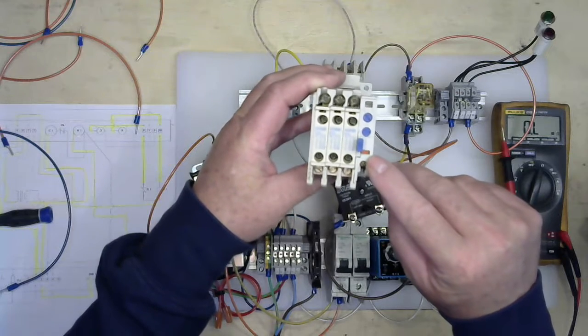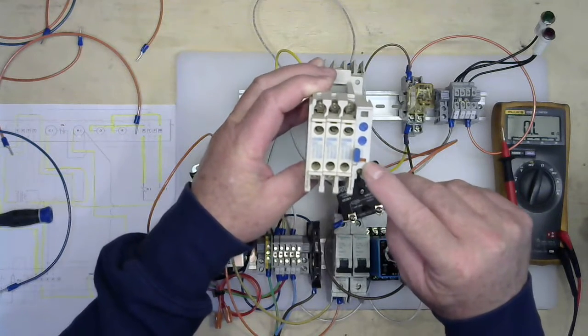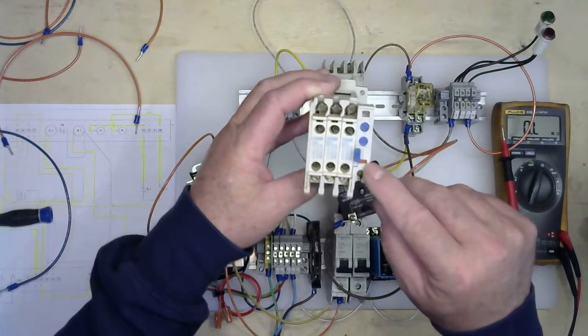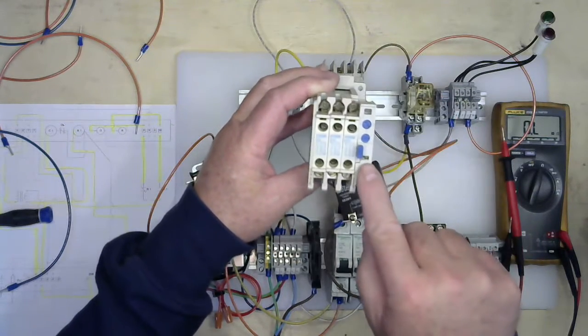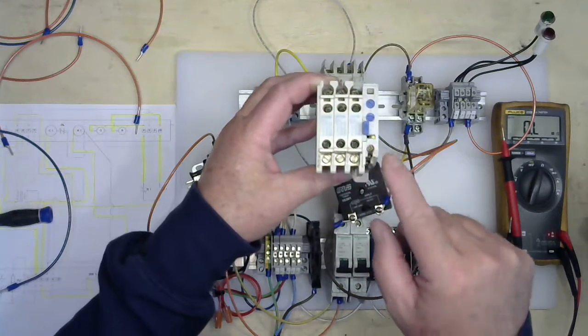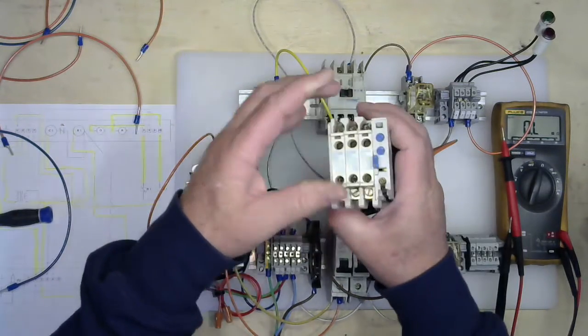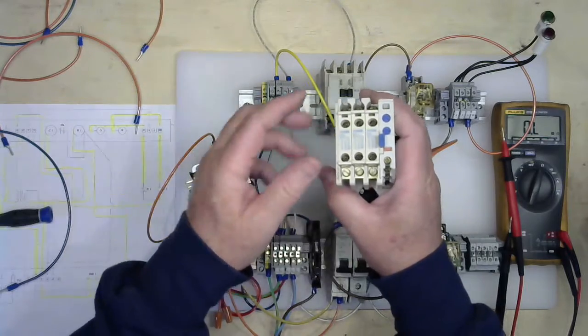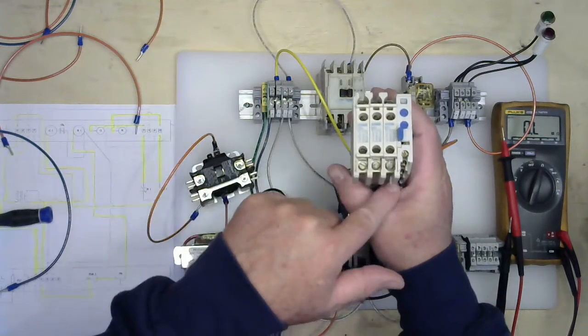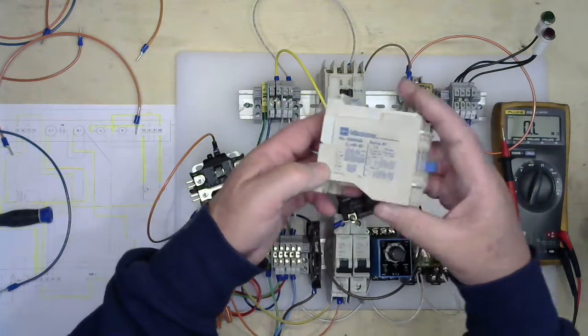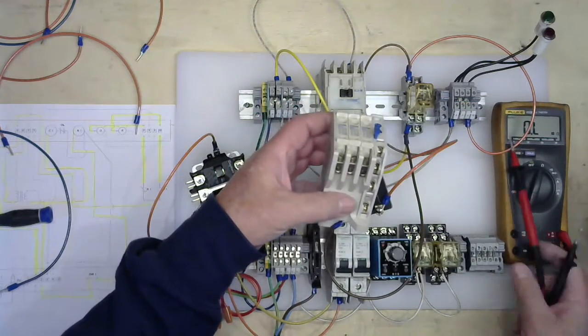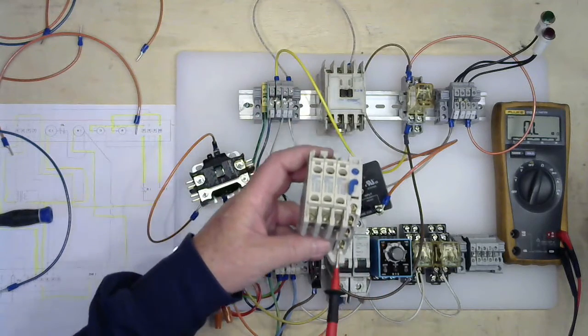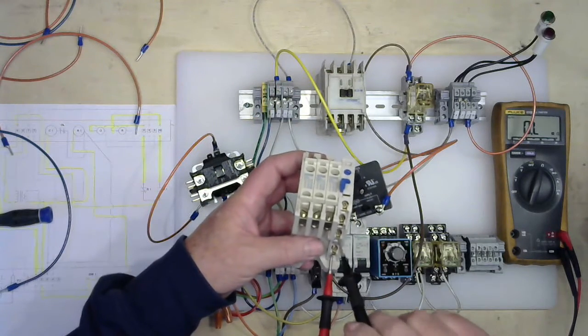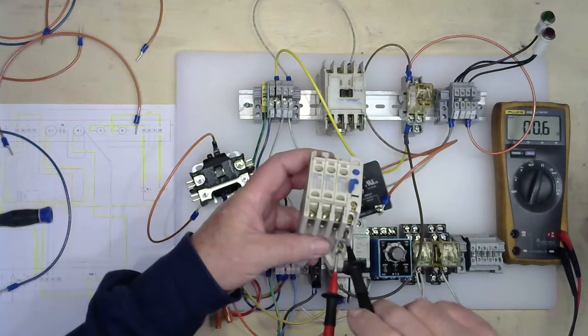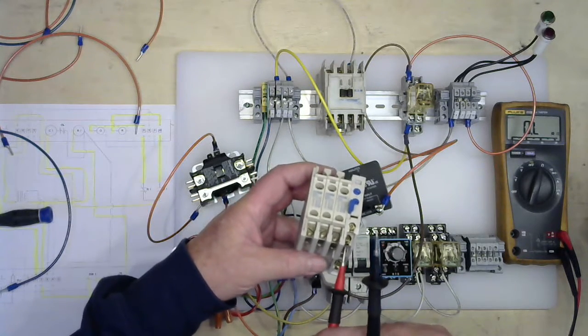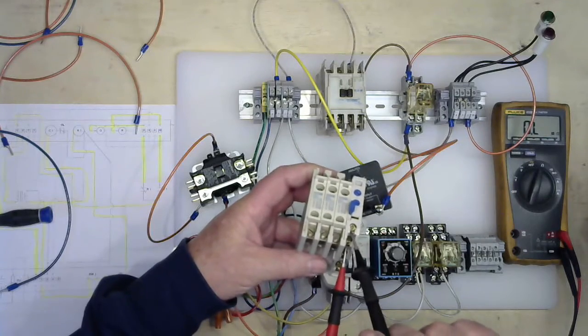Or looking here, I have a red orange indicator light. That is telling me that the overload is tripped. If I hit the reset button, it clears away. So before I determine which contacts I have, make sure it's not in the trip position before you check it out. It's in the reset position, normal position, and our contacts are changed. Let me come back and check my contacts again. My bottom contacts were open. Now they're showing closed. And if I go up to the top, they're now showing open.